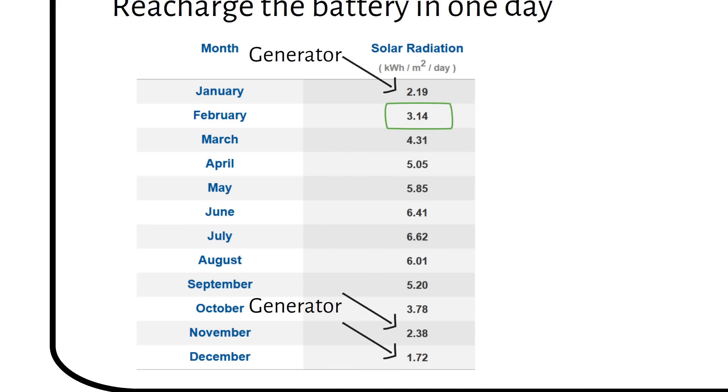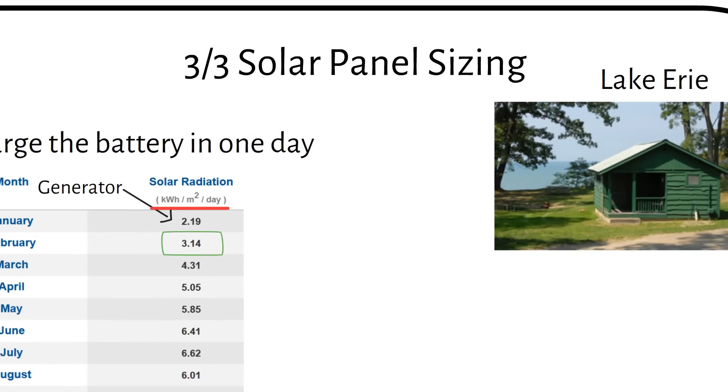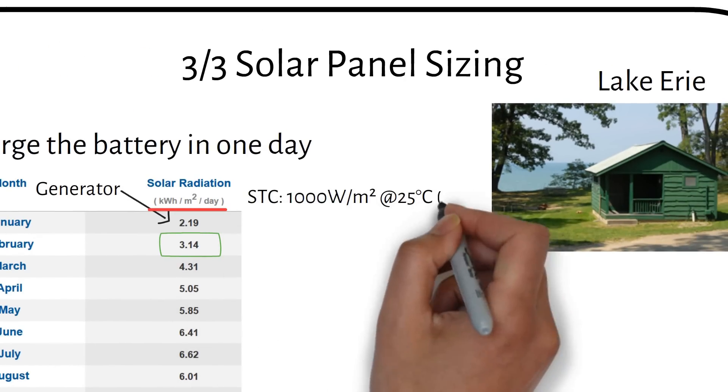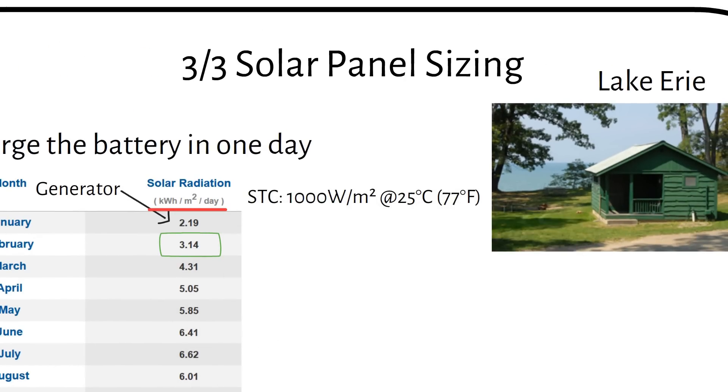We will base our calculation on 3 sun hours. Sun hours is a measurement of the amount of kilowatt hours per square meter per day. Your solar panels are rated at STC or standard test conditions at an irradiance of 1000 watts per square meter. So we can use this to do our calculation without having to use an efficiency factor. All these numbers are monthly averages.